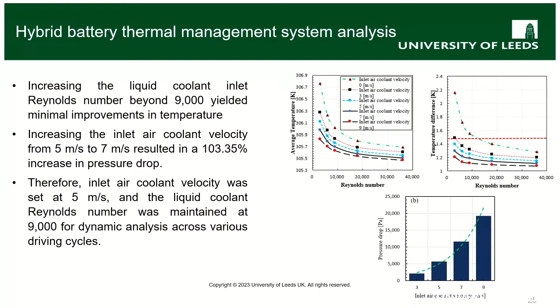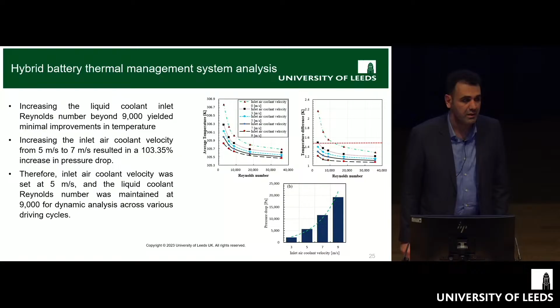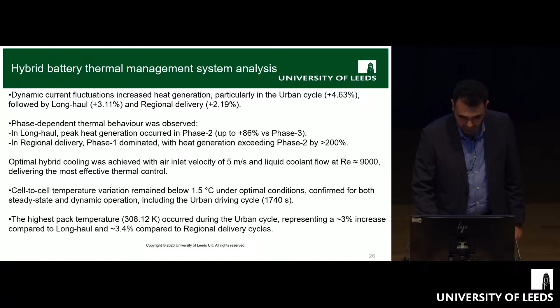We also looked at the inlet air coolant velocity and the pressure drop that we will get. Based on that, we concluded that 5 meters per second would be the economical choice, because increasing from 5 to 7 corresponds to about a 100% increase in pressure drop in our system. So there's a summary of the point.